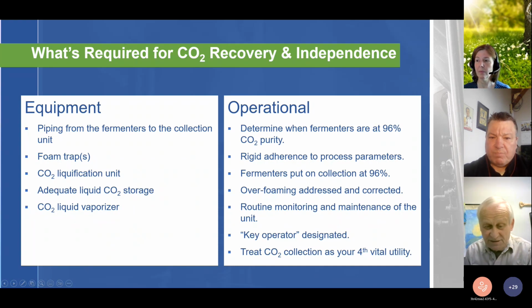Finally, treat CO2 collection as your fourth vital utility. Right now you've got three utility systems, not counting water and electric: steam, refrigeration, and compressed air. If one of those systems goes down, people react. If you want to be independent and self-sustaining on CO2, it becomes your fourth critical utility. If the CO2 collect system goes down, people have to react, whether it's the machine or the brewing process, a foamer, or whatever.